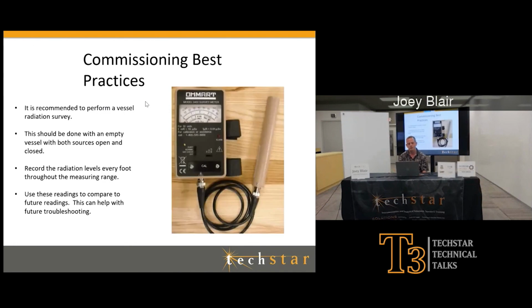All right, so we're going to talk about commissioning. I was talking about a Geiger counter a few times, and there's a picture of one. That's actually my personal Geiger counter in the picture. This is a scintillator tube. I know you probably can't see me, my picture's small. That's the little brown tube at the end. That's what's reading. The scintillation technology is basically the same technology that's inside the detector itself. That's what it's reading.